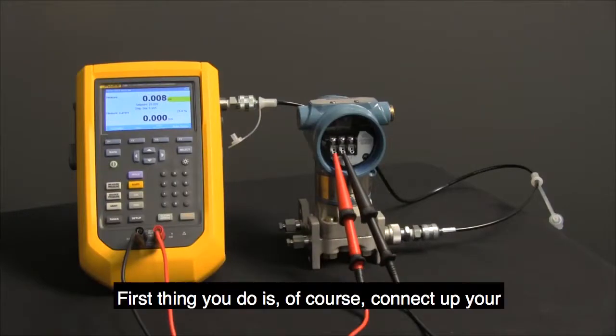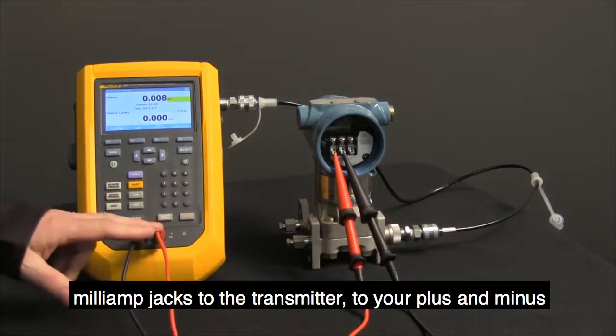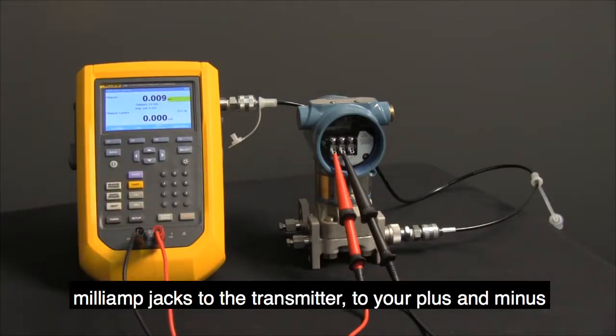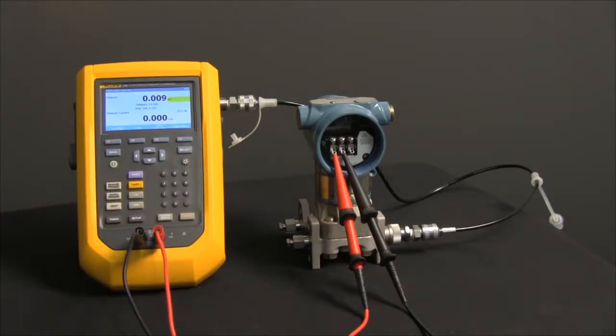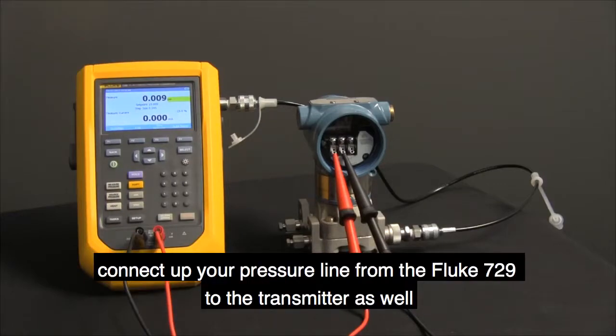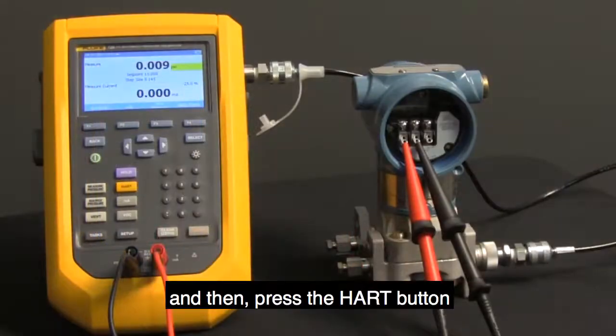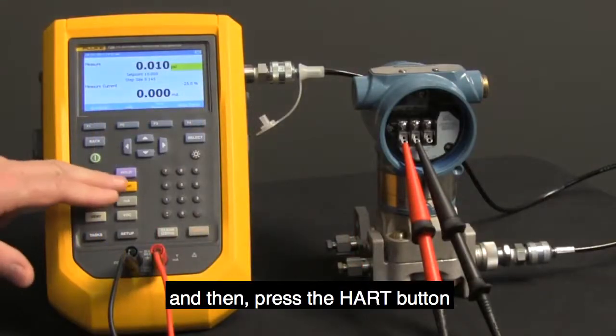The first thing you do is connect up your milliamp jacks to the transmitter, to your plus and minus. Connect up your pressure line from the Fluke 729 to the transmitter as well, and then press the HART button.